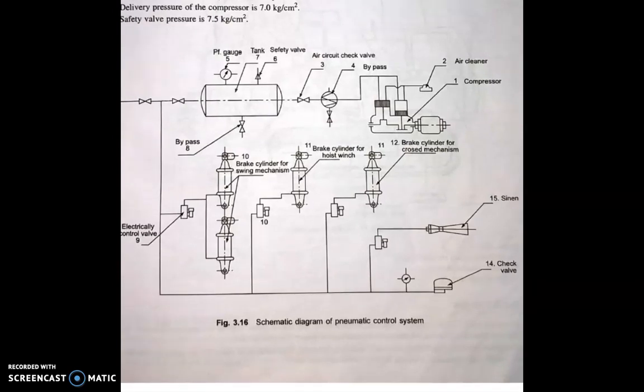Next is the pneumatic control system. This pneumatic system consists of a twin-cylinder reciprocating compressor driven by an AC motor, and delivers air to the tank through an air check valve. The tank is fitted with pressure gauges and a safety valve. Air from the tank is distributed to the swing mechanism brake cylinders, which are controlled through three separately operated solenoid valves. There is one siren operated by air through another solenoid valve. The remaining end is connected to a T-valve for any other auxiliary use. The delivery pressure of the compressor is 7.0 kg per square cm and the safety valve pressure is 7.5 kg per square cm.